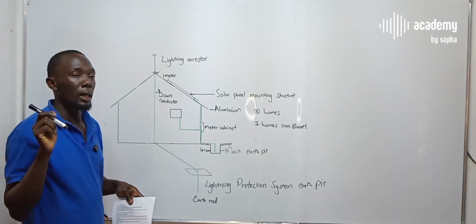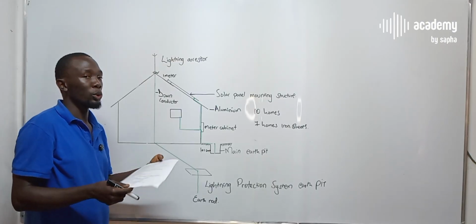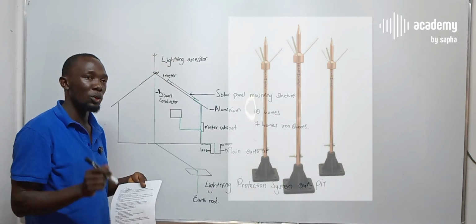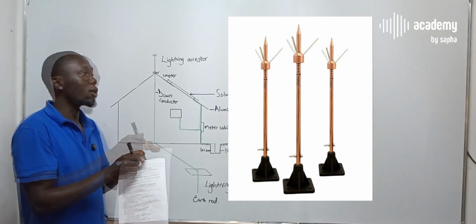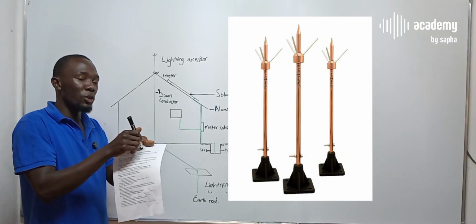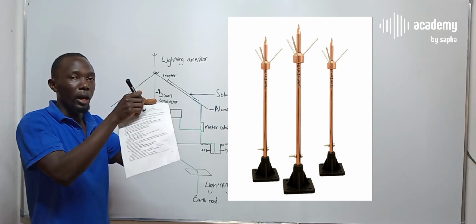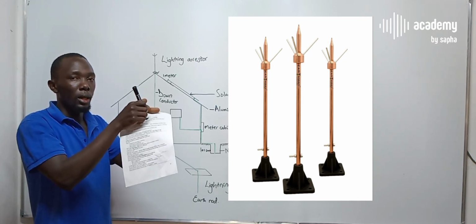According to regulations, you're supposed to have insulation, a non-conductor material, for the very basic systems between the base of the lightning arrestor and the aluminium surface of your roof. That is one regulation most people overlook.